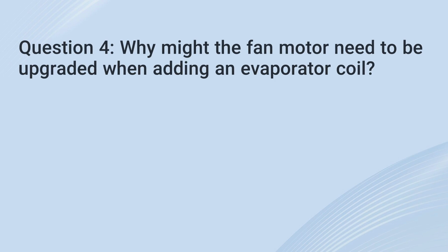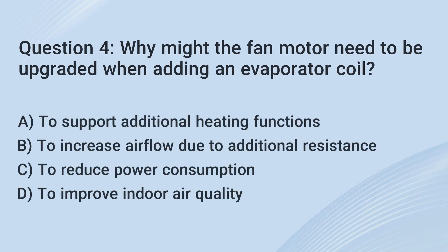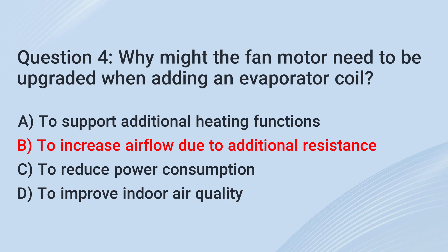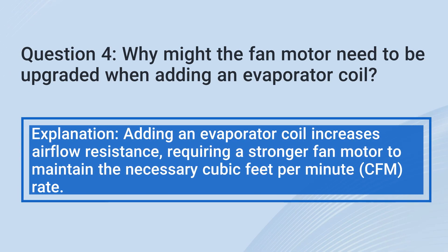Question 4: Why might the fan motor need to be upgraded when adding an evaporator coil? a. To support additional heating functions. b. To increase airflow due to additional resistance. c. To reduce power consumption. d. To improve indoor air quality. The correct answer is b: To increase airflow due to additional resistance. Explanation: Adding an evaporator coil increases airflow resistance, requiring a stronger fan motor to maintain the necessary cubic feet per minute (CFM) rate.